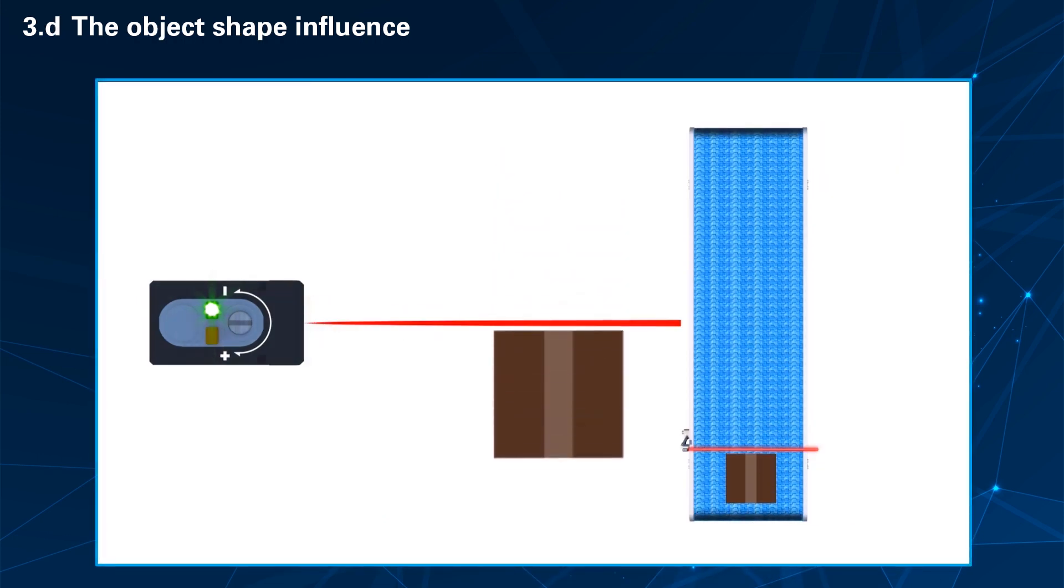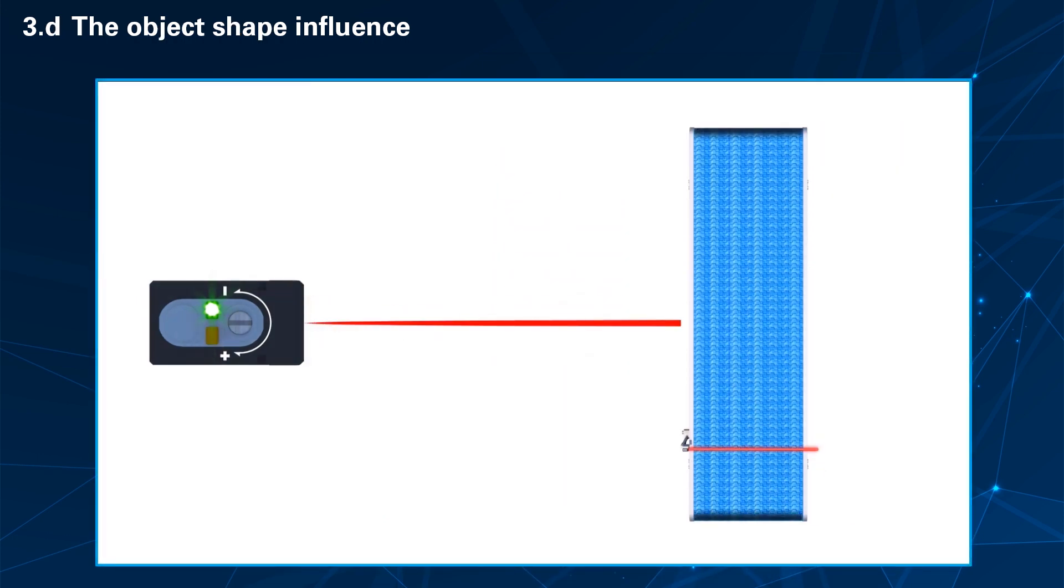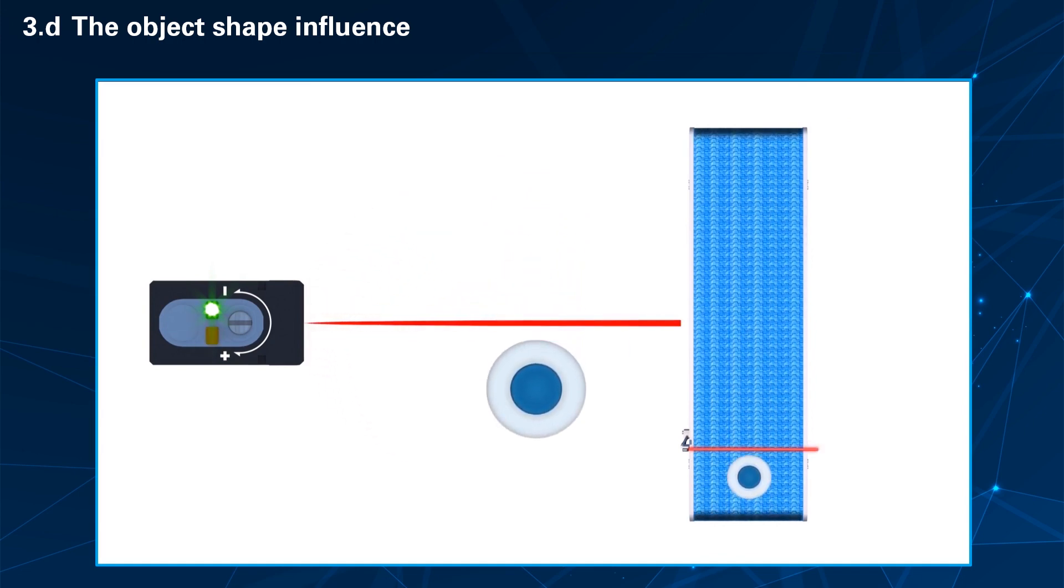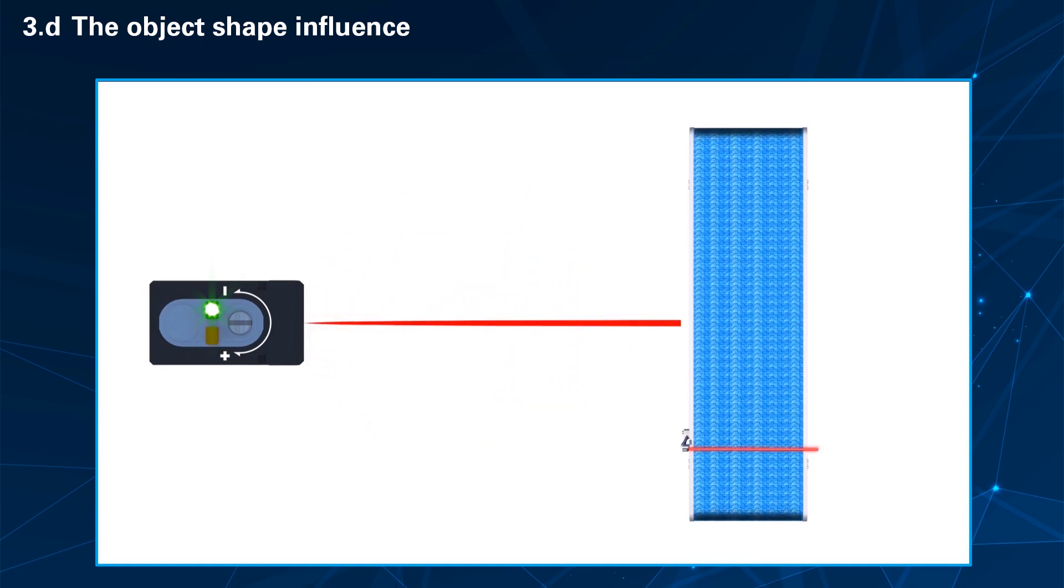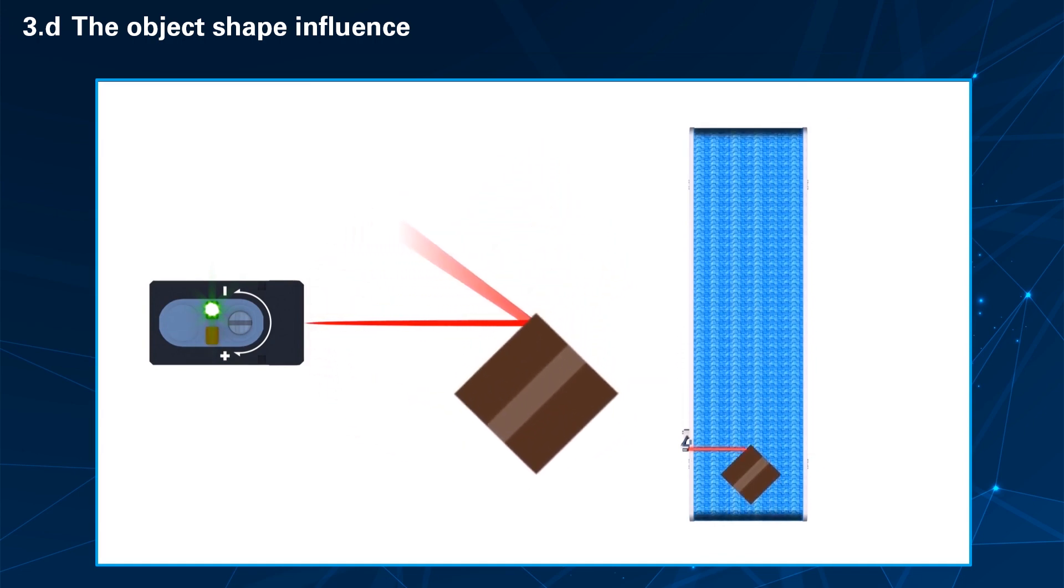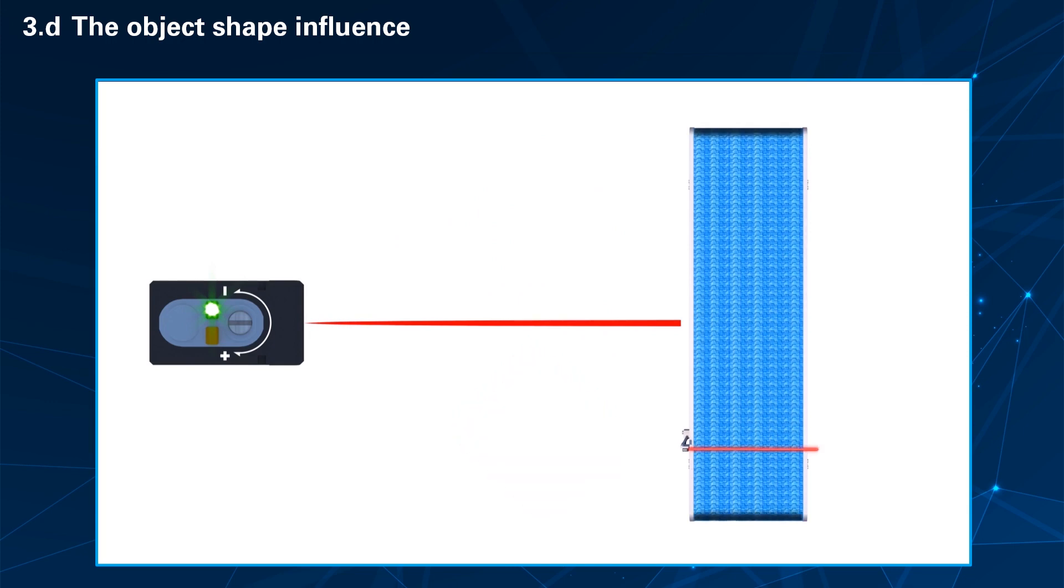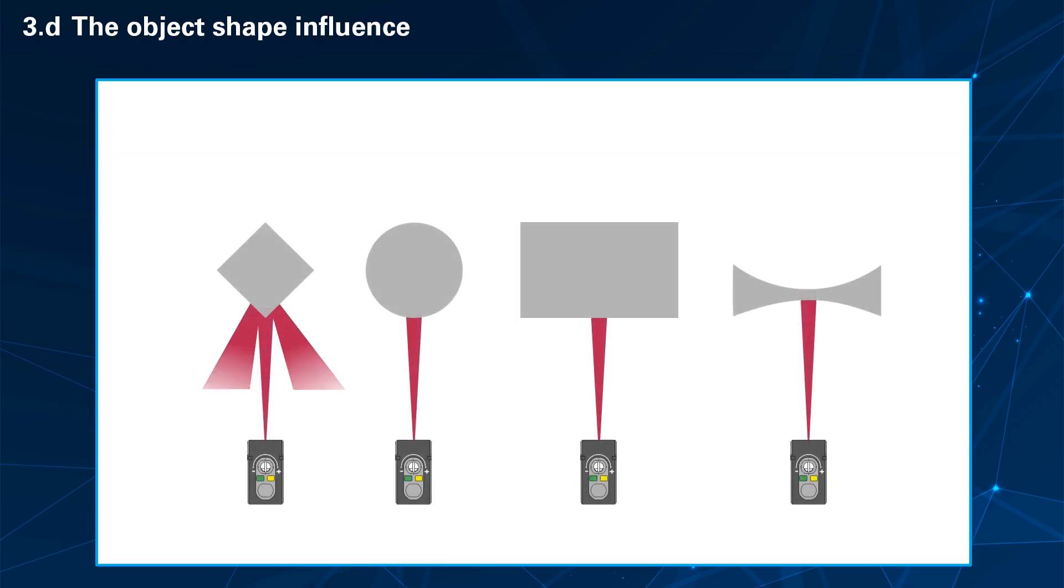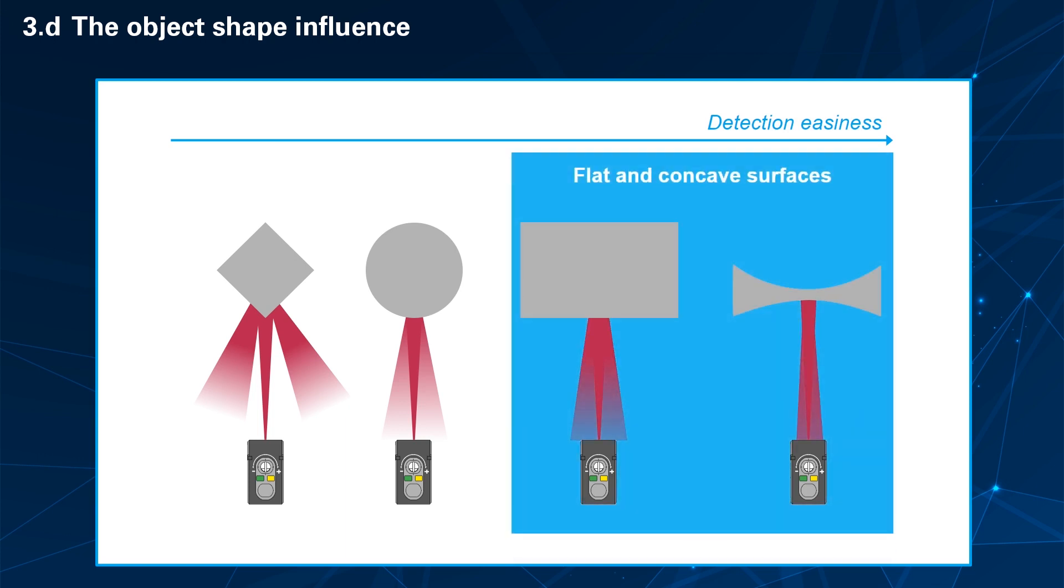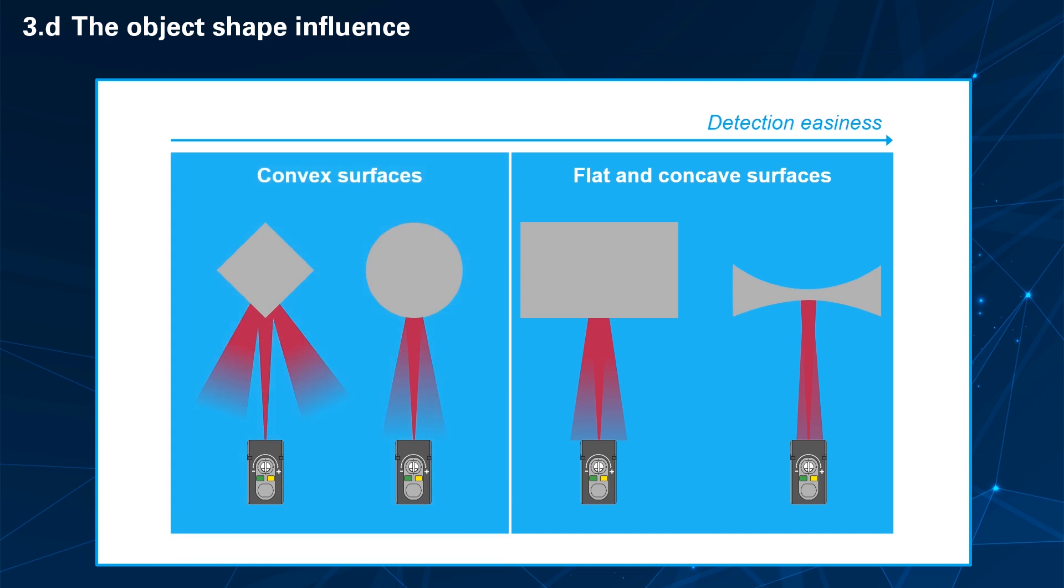The object's shape can influence the direction where the beam is reflected. If the phototransistor does not receive enough energy, the object won't be detected. To be detected, the object shall reflect and diffuse enough energy to the photoelectric sensor. Regarding detection easiness, flat and concave surfaces are more favorable than convex surfaces.